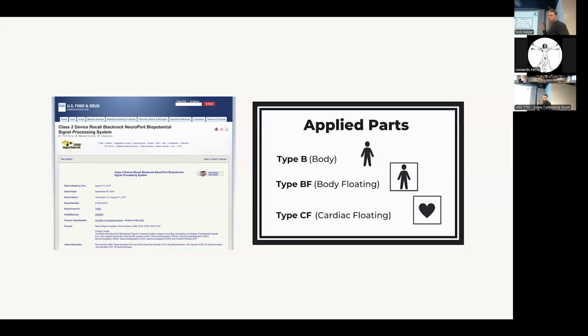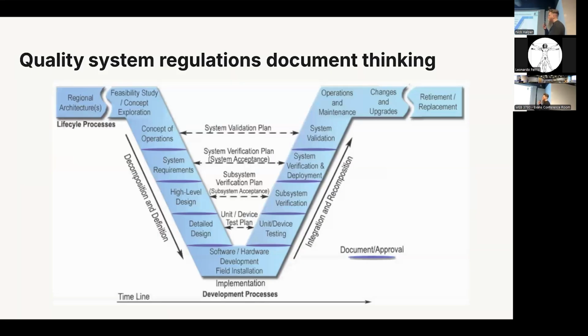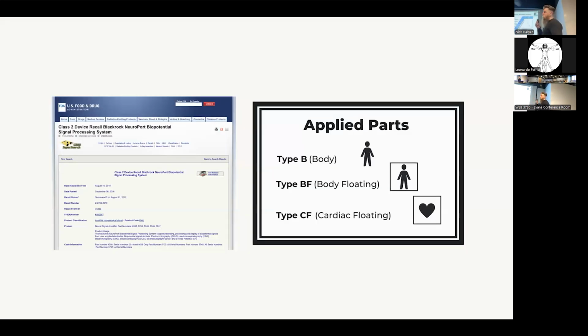But they're connected, right? Coming back to this idea of the V, one of the things standards like 13485 encourage you to do is to create all these traceable links between what your requirements are, what your design outputs are, and what your testing is to show that those meet those requirements. And oftentimes flowing out of that is labeling itself. So when Blackrock thinks about what its device requirements are, it's thinking about what type of stimulation it has to have, how isolated it has to be based on the area of the body we're stimulating, and what sort of safety factors are required. And in doing that, you define this level of applied part.